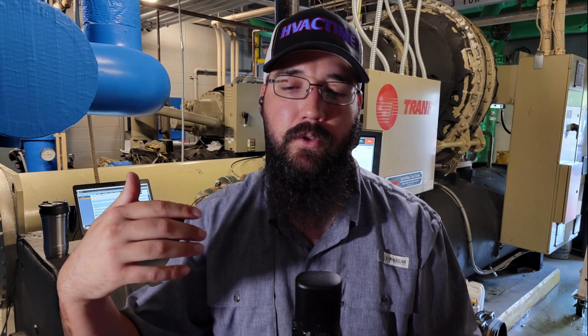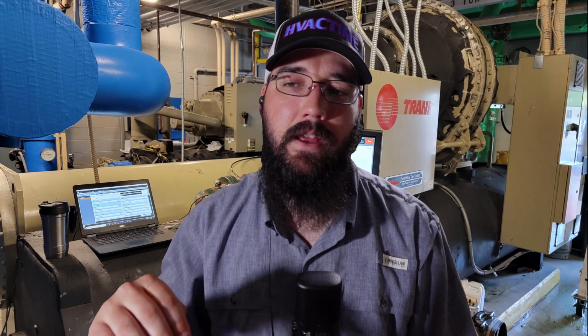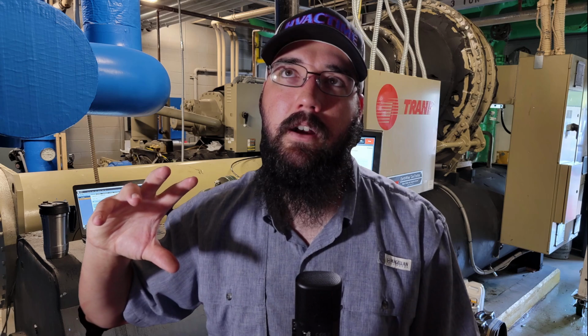So just be aware of that. Why some meters may give a pulsing, those are more of a live feed, and other meters may not pulse like that. It's because they're using a smoothing algorithm to level it out. You'll see this also in micron gauges. That's another classic example. With a micron gauge, some are a live feed, and that means that the reading on that gauge is the literal instantaneous moment. That is the reading you have, while other gauges are smoothed, meaning it's taking that reading in sections. So every so often it's averaging the total reading and then giving you something on the display. So it looks a lot smoother and more consistent, and it doesn't have some of the fluctuations.